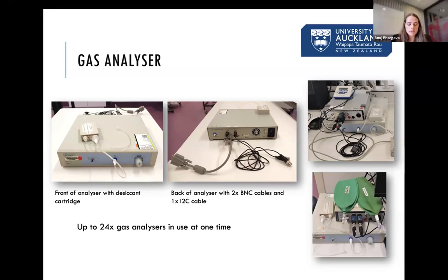The analyzers are fit for purpose, they're easy to use and set up from a technician viewpoint, and they're quite heavy. They take up a bit of space on the bench, but we've come around that issue just by angling the analyzer towards the mixing chambers so that the sampling tube can reach. On occasion, the carbon dioxide and oxygen sensors had to be refurbished, and this is most probably just due to some moisture that somehow got in.